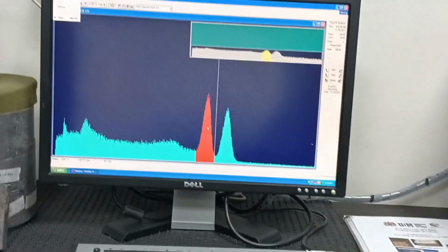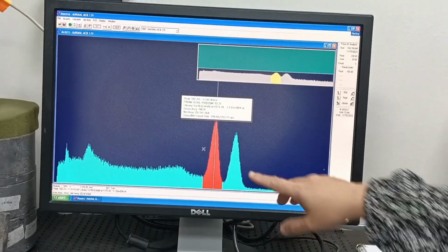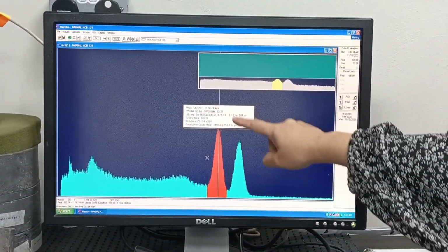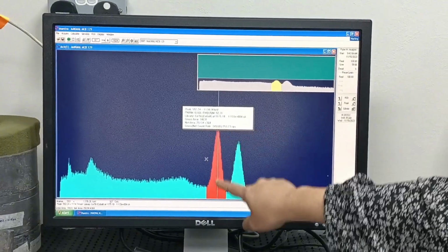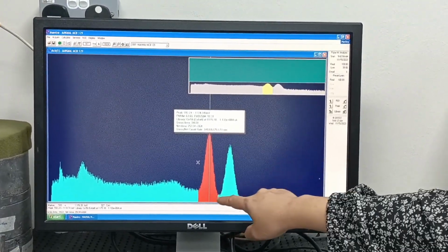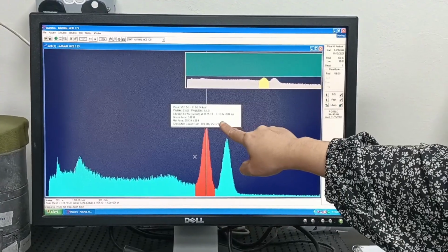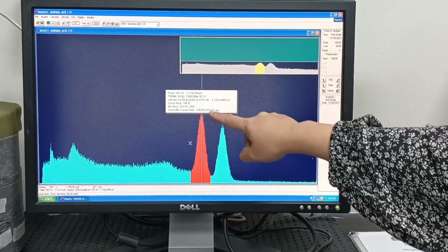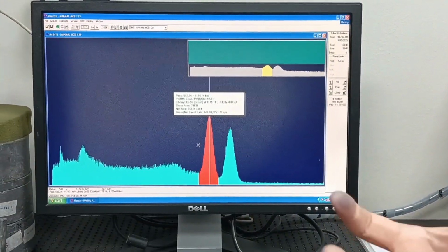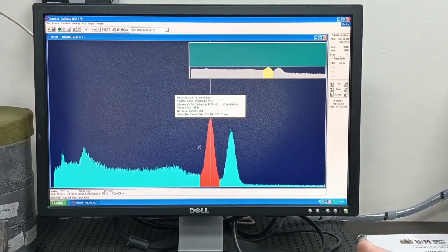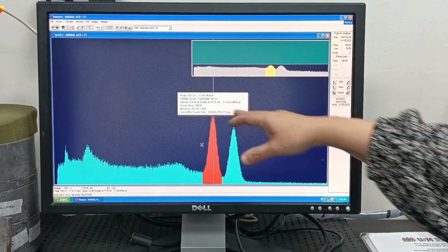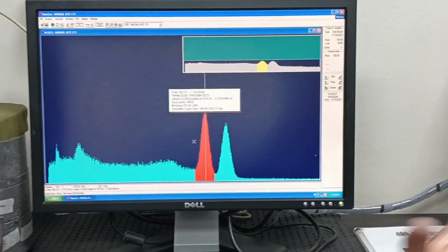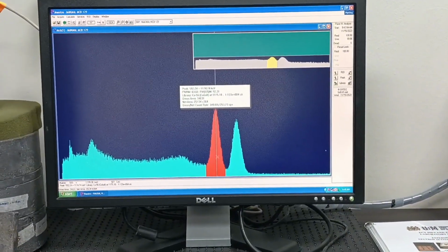And I double click on the peak. So this analyzes everything under the photoelectric peak curve. So you get the gross count, which is the count with the background, or the net, which is the one without the background. So if you are observing gross, it should be gross all the way until the end of your experiment. If you're observing net count, it should be net count until the end of your experiment, so that it is consistent. So now, what is the channel number?